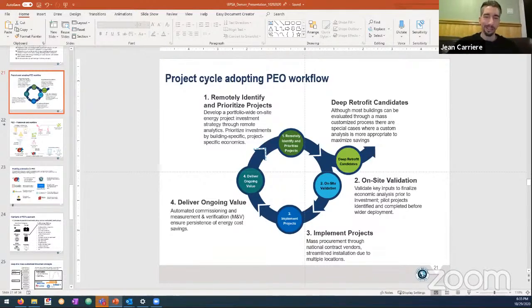Yeah, hey, I had a question. I see the opportunity on mass scale simulation, but the zone-based model, if it's off by that much in the summer peak loads, and you're making recommendations on the mechanical, it's probably going to be off. I just feel like it's a little bit fuzzy. How have you calibrated the geometry impact from the zone-based model to the actual calibrated model? Because I think the shape has a lot to do with it too.